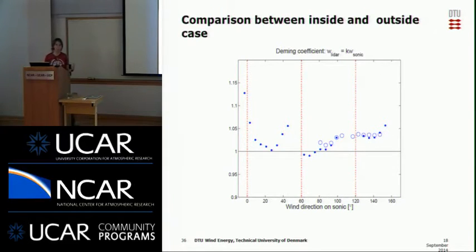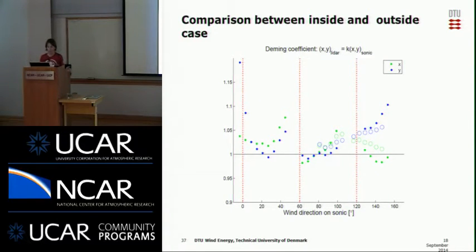And then I added on the Deming coefficient fits for when we measured inside the sonics, and that's these rings here. So the dots are for the outside, the rings are for the inside, and they correspond pretty well. So that also points to transducer shadowing. And the same for the X and Y. The trends are similar here, but maybe not quite the magnitude.